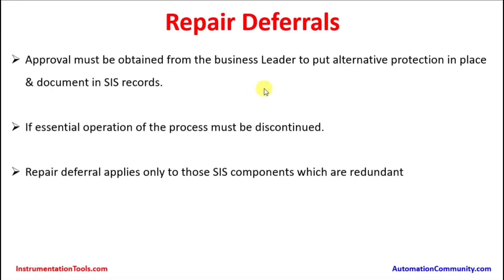Approval must be obtained from the business leader to put alternate protection in place and document in SIS records. Whenever SIS instruments are not available and the plant must continue running, alternate protection is required to maintain the safety integrity of the plant. If essential operation of the process must be discontinued, repairs or proof testing must be completed, potentially requiring a plant shutdown. Repair deferrals apply only to those SIS components which are redundant.